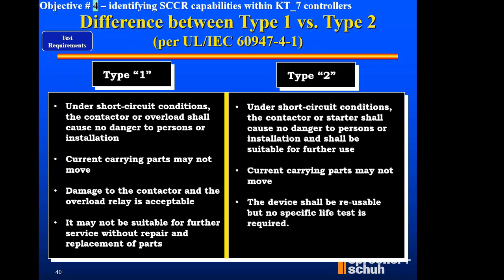Type 2, it's got to be safe. It can't throw parts everywhere, so you're safe in protection. And number 3, instead of not having the ability to continue, under a type 2, the device shall be reusable, but type 2 doesn't say for how much longer. There is no life test required after that.